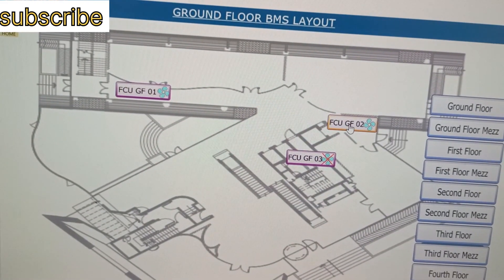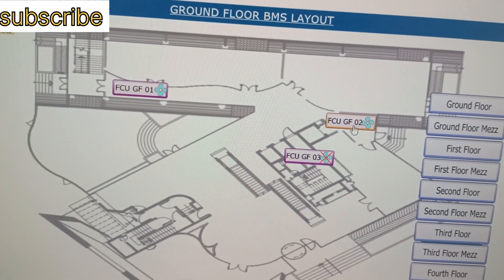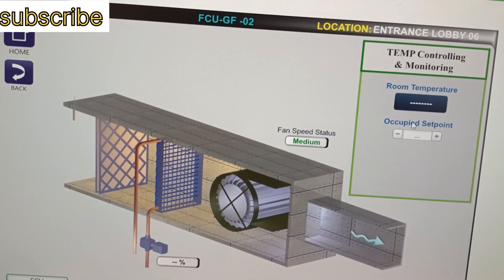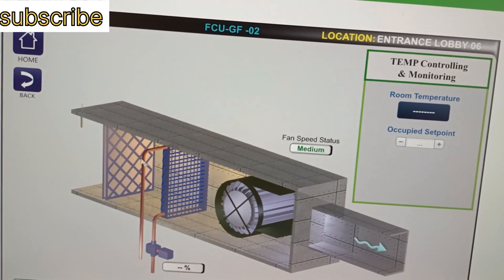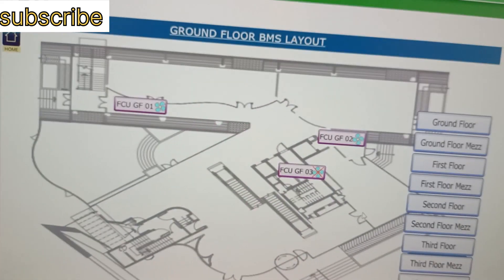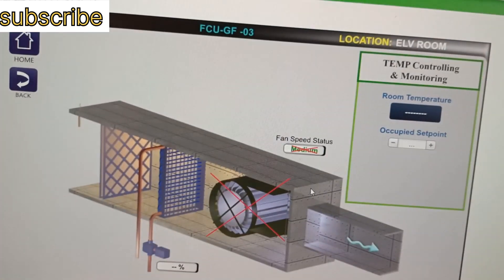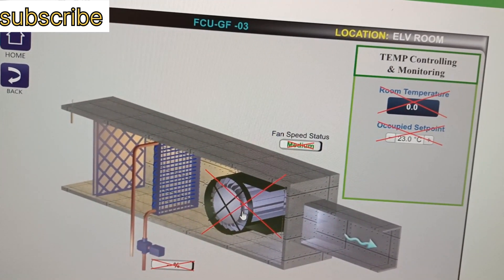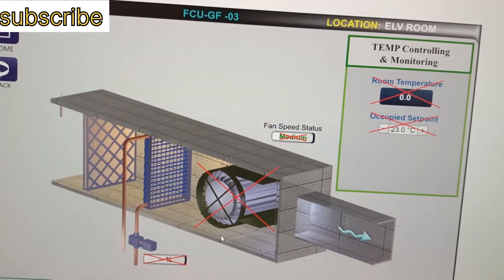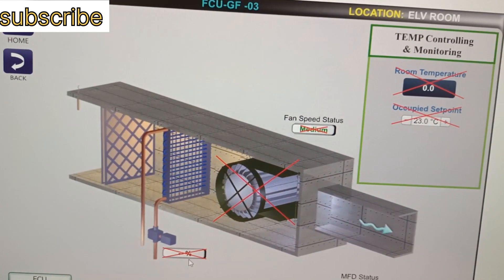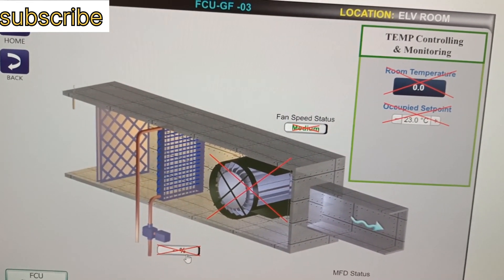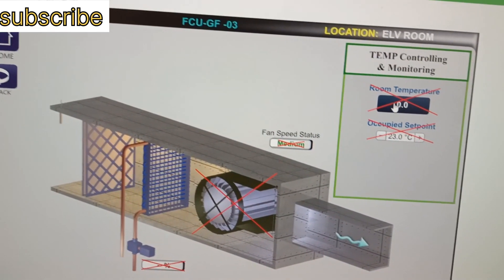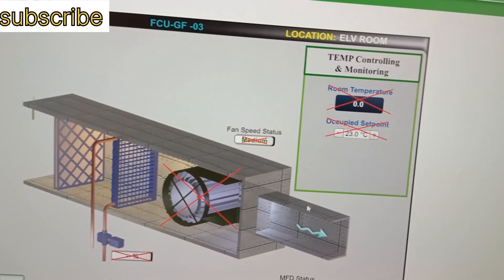FCU GF02 is in off position and there is no temperature shown. We need to check this one. In this parameter we are not getting any running status, and even the coil temperature, the percentage, the room temperature, and the set point — we are not getting any of these readings.